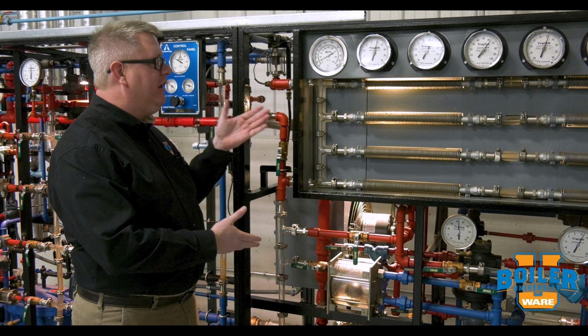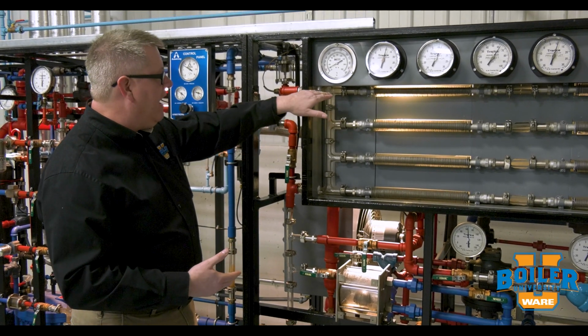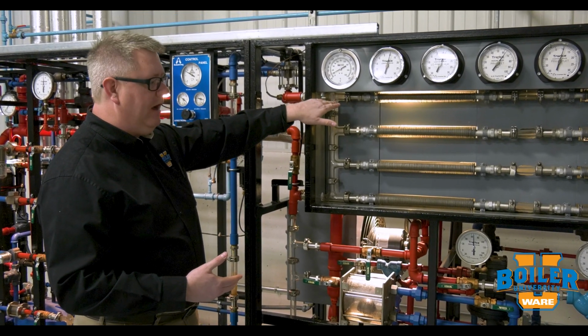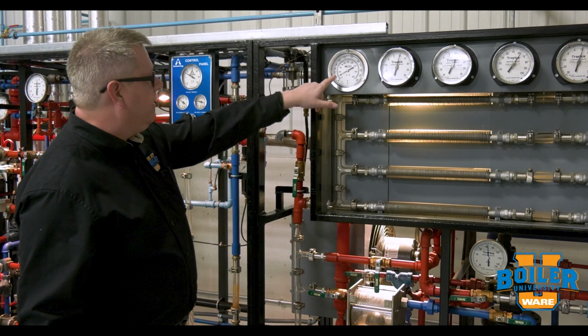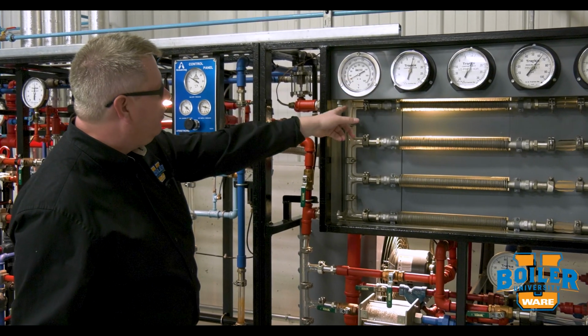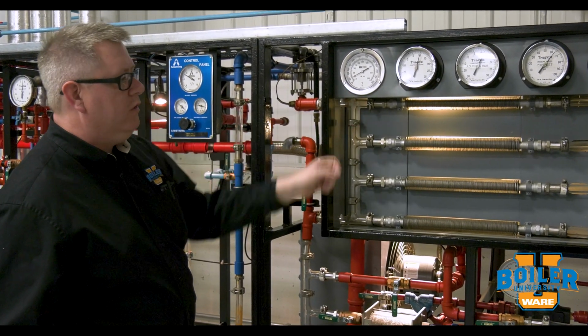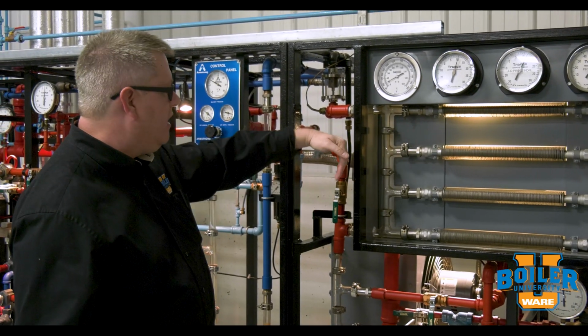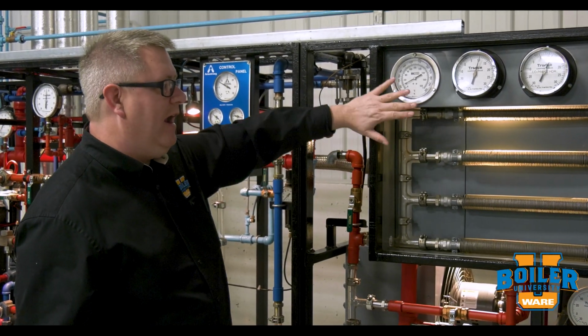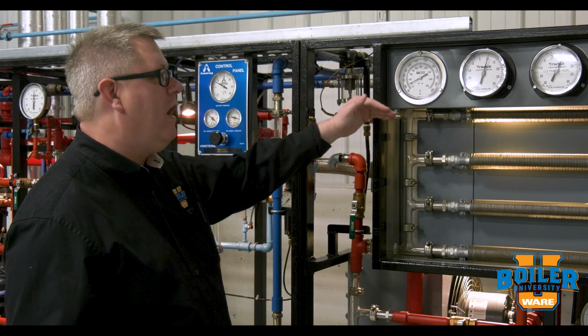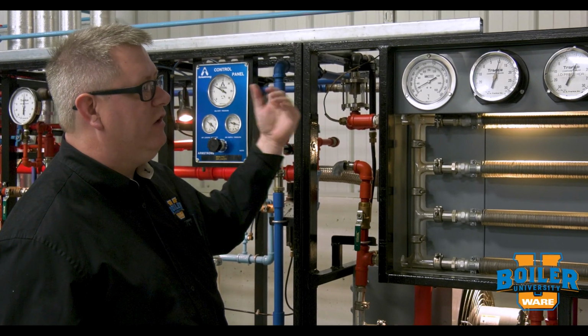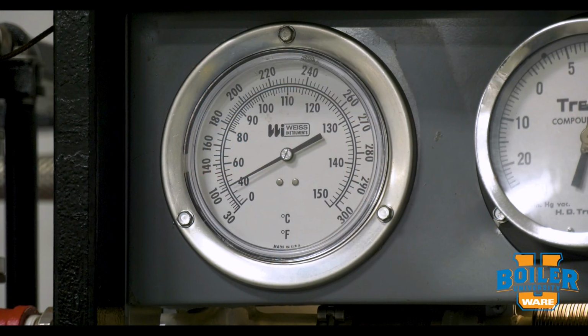What we're seeing on this heat exchanger, though, is that we've got a high point that's holding air. We know that because we can look at our temperature indicator right here at the top left corner. We've got steam coming in that end, condensate leaving this end, and air trapped in this corner. So our outlet temperature is actually lower than what we should be seeing.